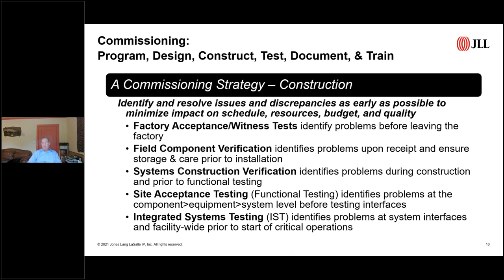When everything's been functionally tested and seems to be working properly, we usually end up with what we call a pull-the-plug test, where we kill power to the entire facility from outside the site, maybe by having the utility open their feeder breakers, and watch that the building responds appropriately—that the emergency generators start, the UPS carries the load during the outage, the chiller plant restarts, and the building survives the outage without any impact to the mission.